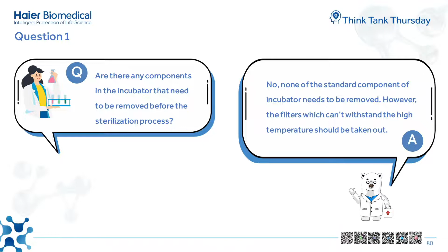Question 1: Are there any components in the incubator that need to be removed before the sterilization process? No, none of the standard components of the incubator need to be removed. However, the filters which can't withstand high temperature should be taken out.